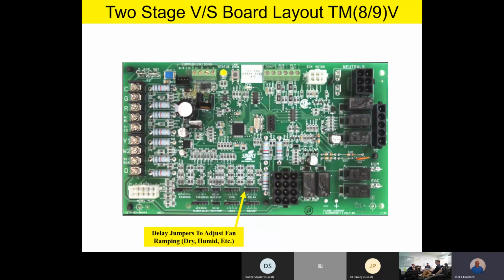The delay jumper is actually a cooling on delay function. And so based on your local geography, for instance, I happen to remember that the B is for humid. And I like to remember that because I live down here in Mobile, Alabama. So B for Mobile, right? And so the B configuration, what that does is it sets the airflow in this cooling on delay function. So based on your geography, we have A, B, C, and D. And if you look in your service information that comes with the equipment, in the install guide and technical guides, you're going to find that this is very, very well explained.